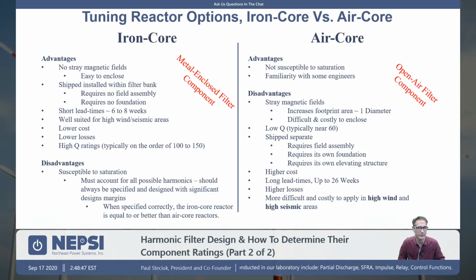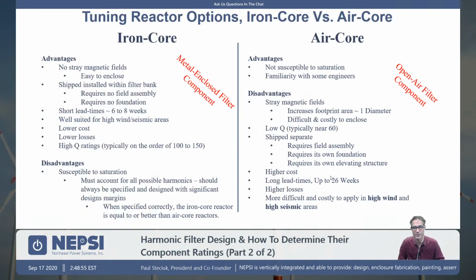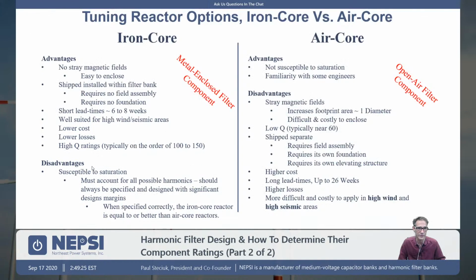The lead time for iron core reactors is typically 6 to 8 weeks, versus air core reactors, where we're up in that 26-week lead time, so much longer lead times for air core reactors. Because the iron core reactors are put inside the enclosure, they are well suited for high wind and high seismic areas. Air core reactors are typically stacked up inside the substation because they're high. They're not well suited for high wind and high seismic conditions. So there are some disadvantages. The key disadvantage of the iron core reactor is that it can saturate. Okay, if it's not properly designed or specified, it can saturate.